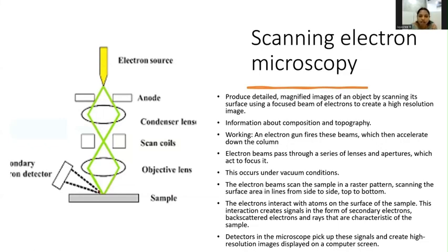So when you are using electron microscopy with a non-conducting sample, you will encounter a lot of problems when getting the images, like the charging which happens on the surface of the sample. For example, polymers are not conductive, and organic materials are non-conductive, so the electron source is not going to image your sample properly. The charges just accumulate on the surface and you do not get a clear image.